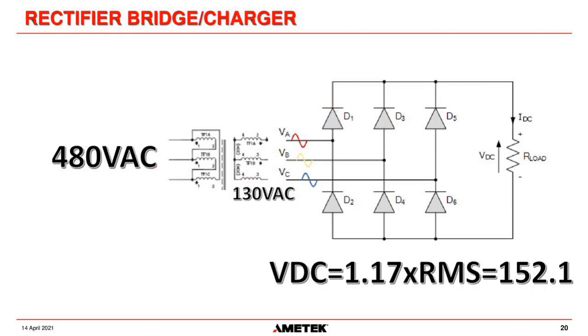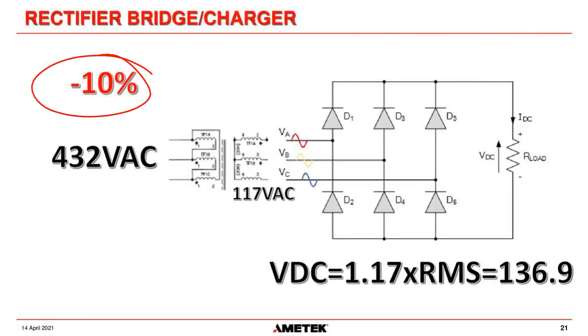But our chargers have a tolerance, we can go down to minus 10%. So that means our chargers should be able to operate with 432 volts going in. Now, the direct ratio equation: if it's 10% on the primary, then it's 10% on the secondary, so that goes down to 117 volts. And if we use the calculation, 1.17 times 117 volts, that goes down to 136.9 volts. So with a change on the AC input, you can see that has a change on the DC output.